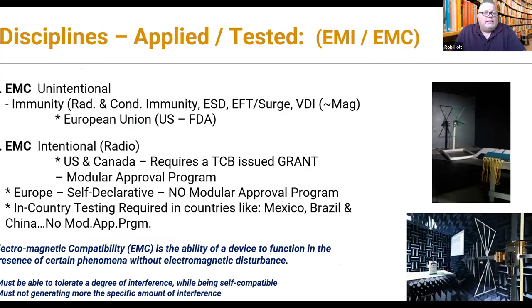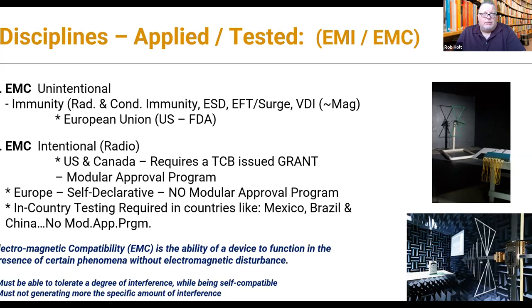Moving into EMC — within EMC you have unintentional, meaning not intended to radiate, and intentional, which is a radio device. Electromagnetic compatibility is defined as the ability of the device to function in the presence of a certain phenomenon without electrical disturbance. It must handle a certain degree of interference while being self-compatible and must not generate more than a specific amount of interference. In Europe, this is required. The FDA for medical devices has also required a suite of susceptibility tests, including radiated and conducted immunity, electrostatic discharge, electrical fast transients, surges, voltage dips, and interrupts representing a brownout situation.